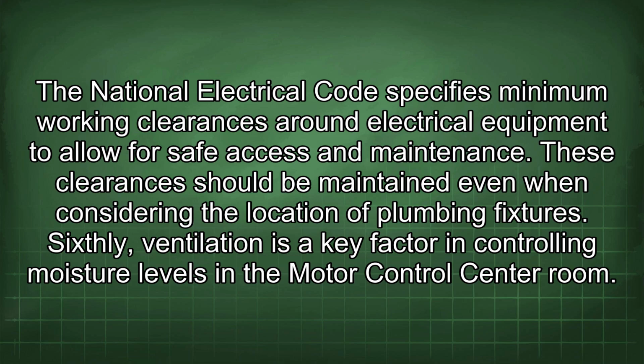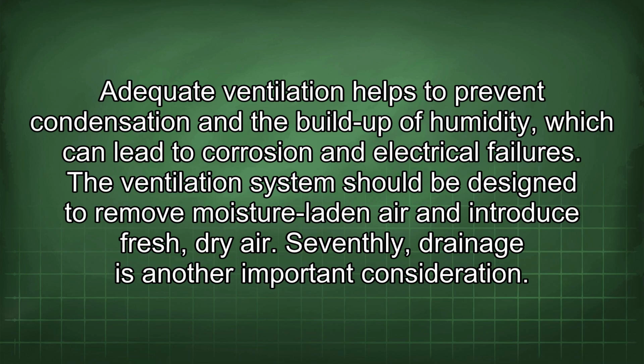Sixthly, ventilation is a key factor in controlling moisture levels in the motor control center room. Adequate ventilation helps to prevent condensation and the build-up of humidity, which can lead to corrosion and electrical failures. The ventilation system should be designed to remove moisture-laden air and introduce fresh, dry air.